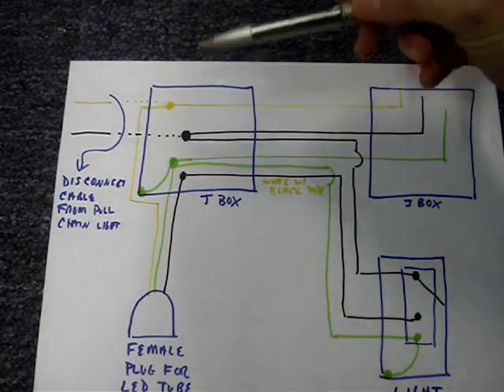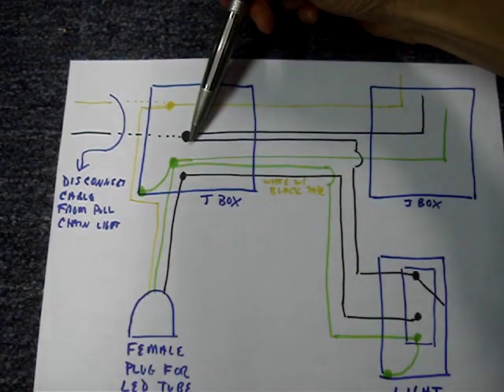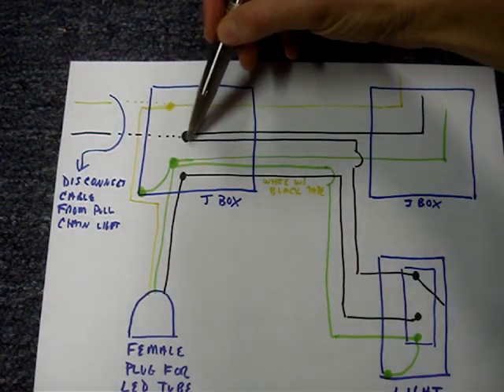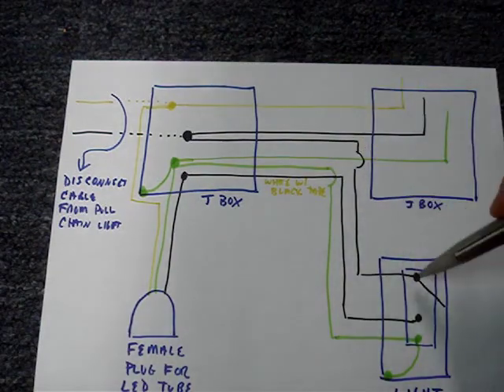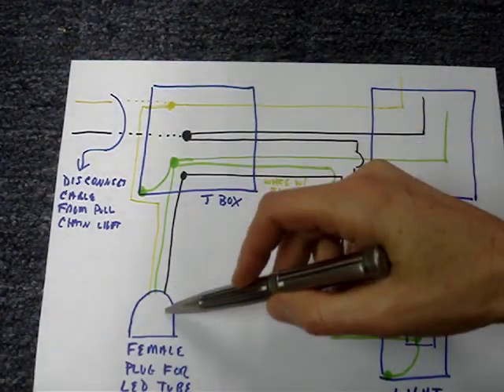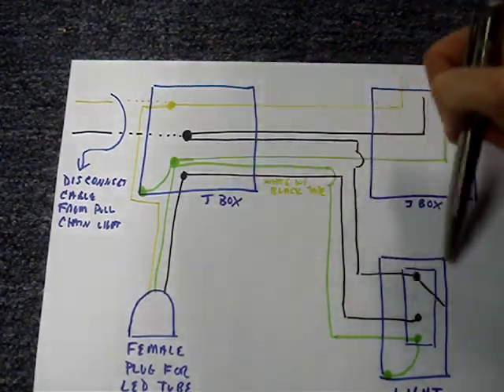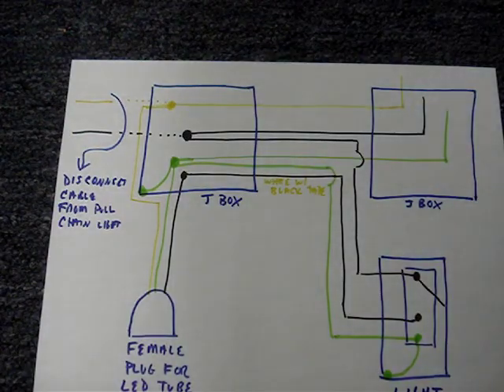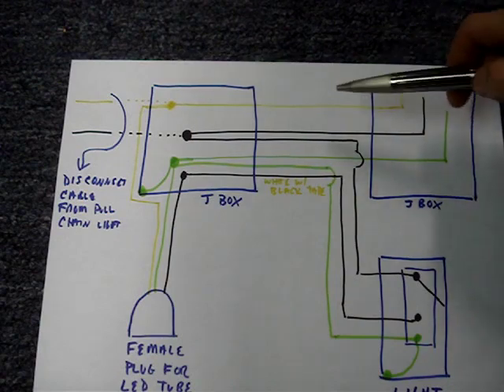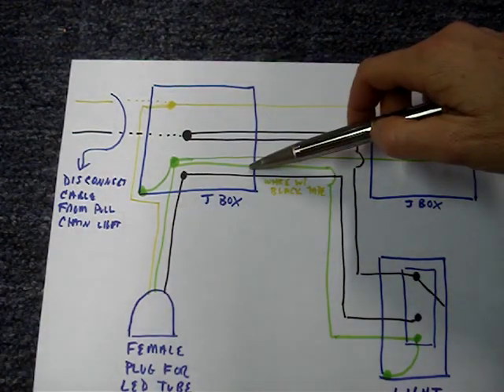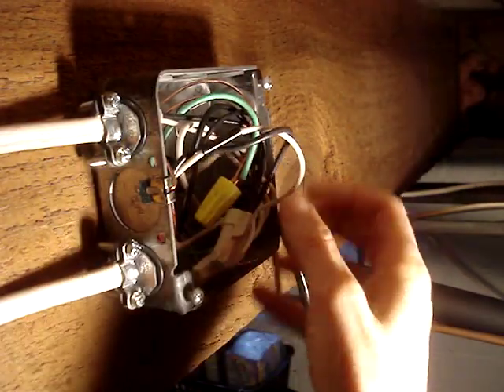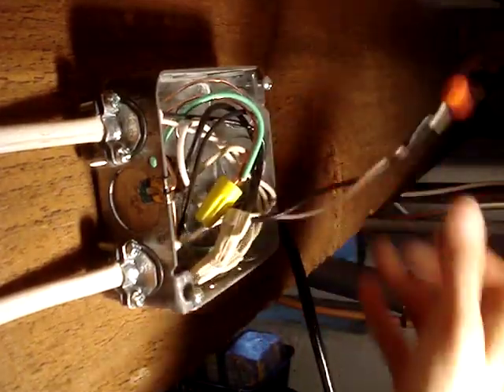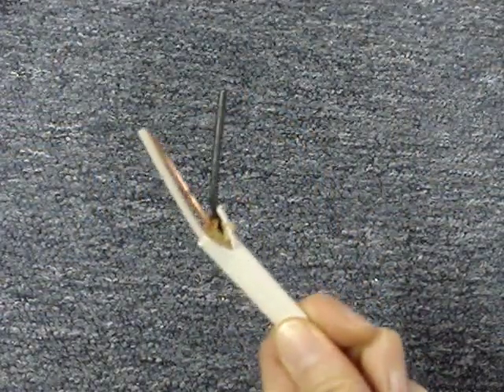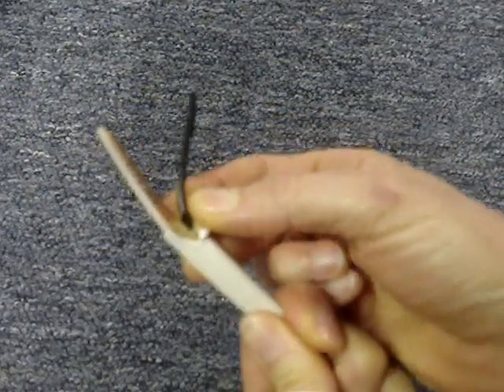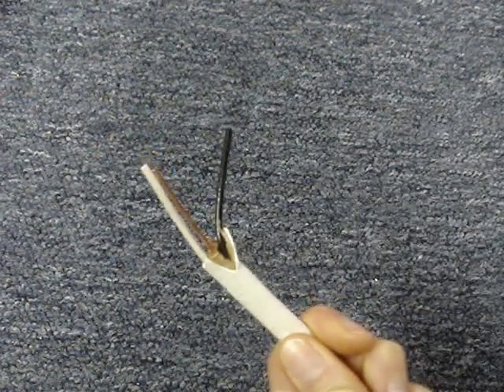Next, I moved my meter lead to this black wire, and I read all the way through the black wire. I had the light switch closed all the way back and down to here. I read between ground and the whole hot wire, and I read an open. I didn't read a short between the hot and the ground wires like I thought I should. It's possible that after I pulled the wires out of the box, the black wire and the ground are no longer touching each other. I carefully examined the wiring in the box for any nicks in the coverings. I paid close attention to where it was trimmed back from the jacket. I couldn't find anything damaged.